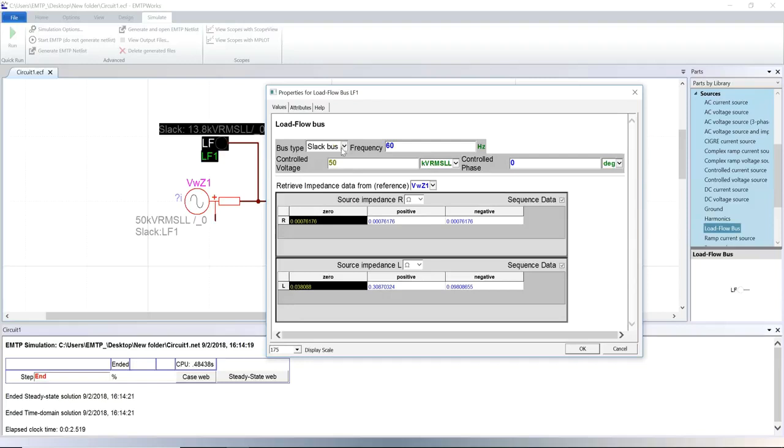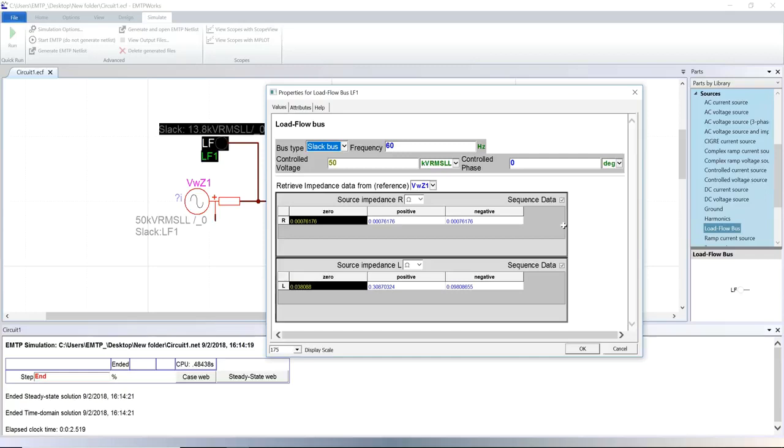Network equivalencies are often represented by slack buses or infinite buses. In this case, the voltage and its angle must be entered. There must be at least one slack in the circuit to perform the load flow calculation.